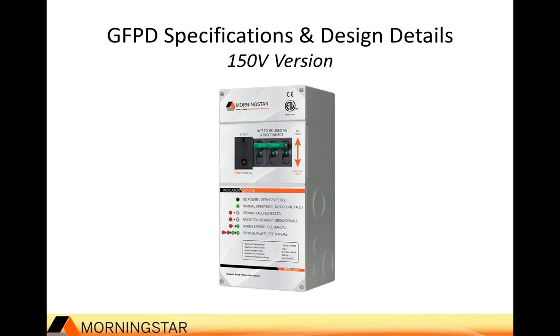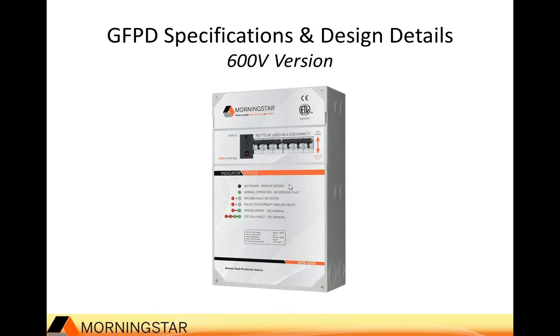Okay, so here's some examples of the products. In this case, this is the 150 volt version. You can see we're breaking both legs, and then this is the trip breaker on the end. So when that is thrown, it takes both the positive and negative with it, and the entire system is disconnected. And these conduit boxes are designed and made up with the TriStar MPPT 150 and also with the 600 volt.